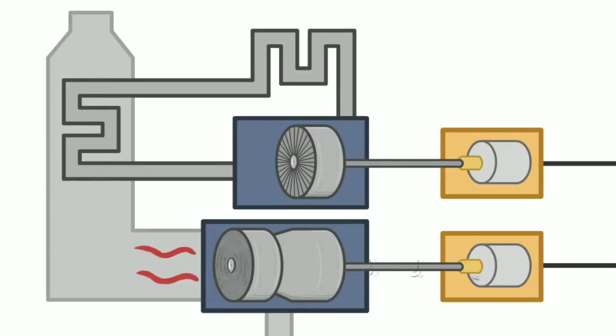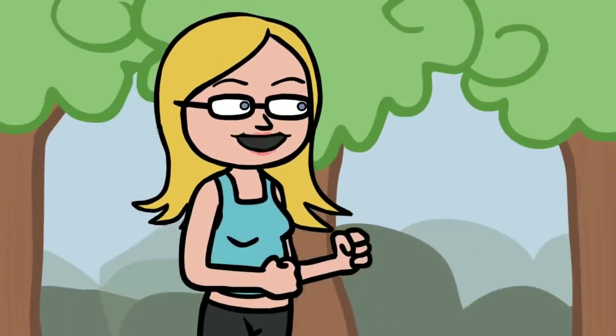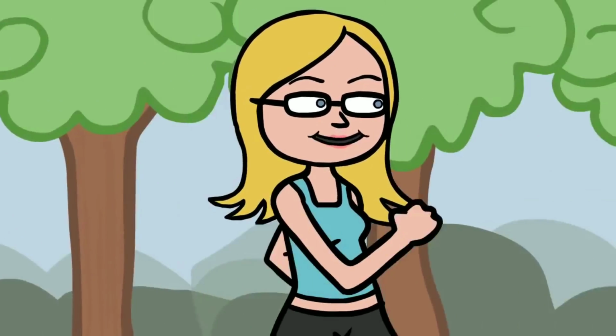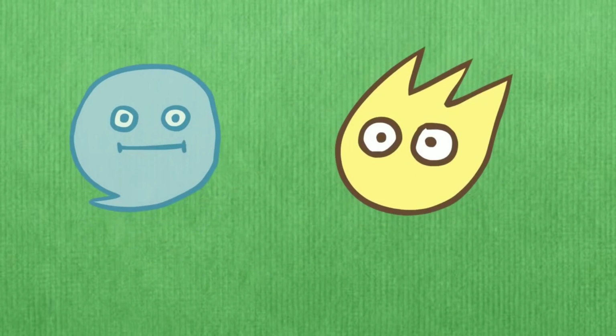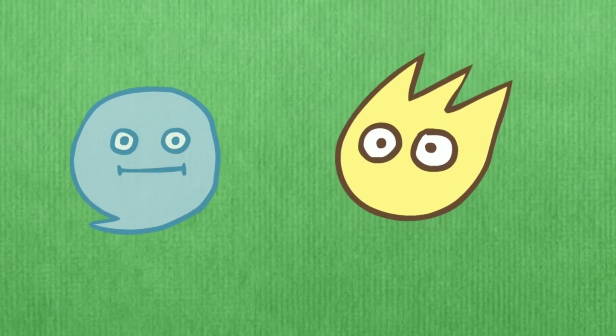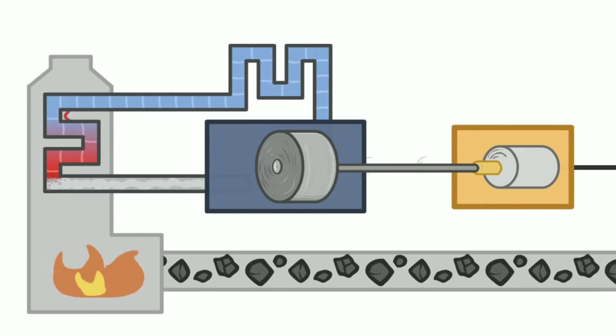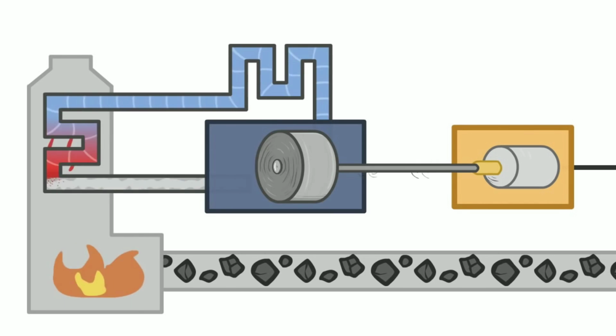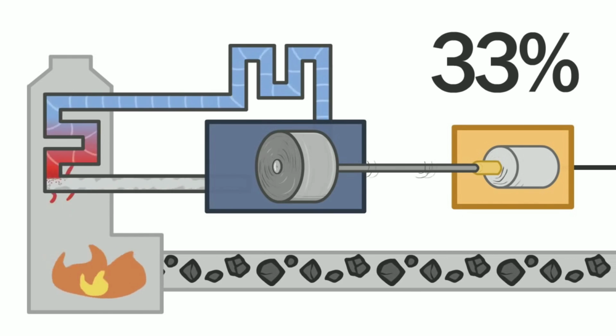But instead of using coal, or even more gas to create steam, a combined cycle plant uses the exhaust heat from the gas turbine to boil water into steam. The steam then drives a second turbine, which spins a second generator, producing even more electricity. This two-step combined cycle process is highly efficient, converting as much as 50% of the energy contained in natural gas into electricity. In comparison, coal-fired steam turbines are only about 33% efficient.